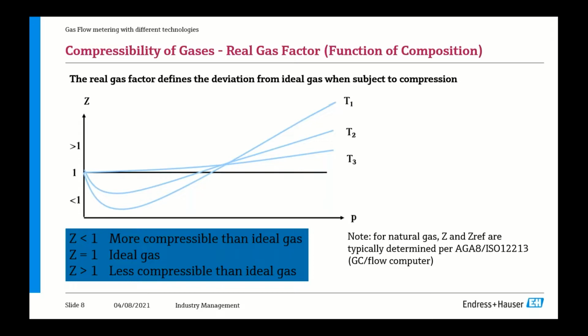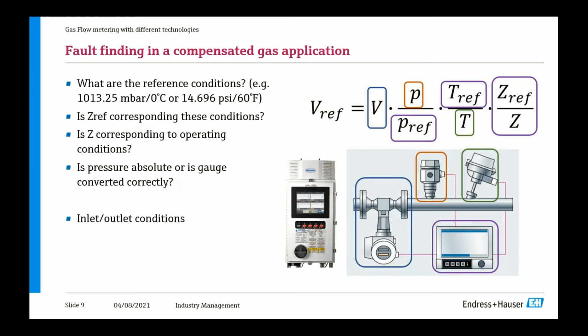So if we go to the next slide, here we see the different sources of error you have in a volumetric solution that has to be compensated, because corrected volume, normal meters cubed or standard cubic feet, they are referring to a certain reference condition, like 1013 millibar or 14.696 psi, and a certain reference temperature, 0 degrees C or 60 Fahrenheit. So you have a lot of different sources of error. If you compensate a DP solution, if you compensate a volumetric solution, you need to make sure pressure is correct, because are you using gauge pressure or absolute pressure, which is a potential error. You need inlet runs, outlet runs.